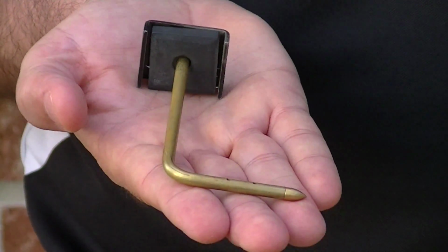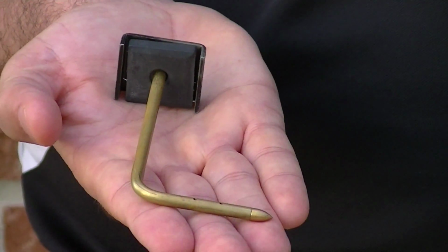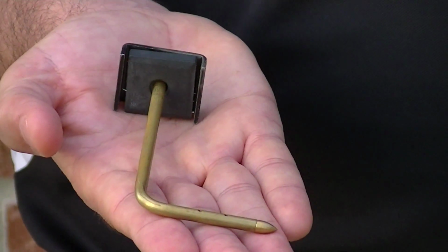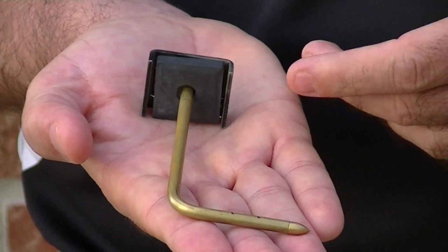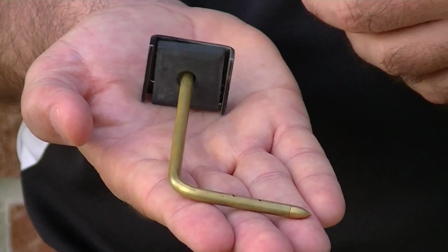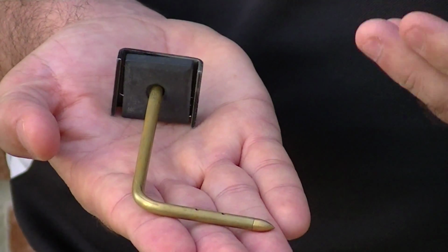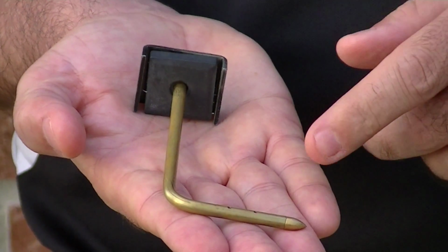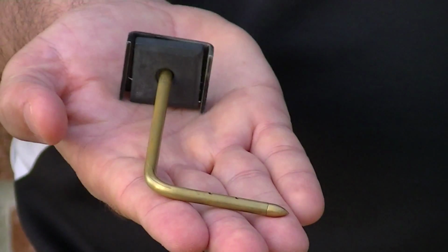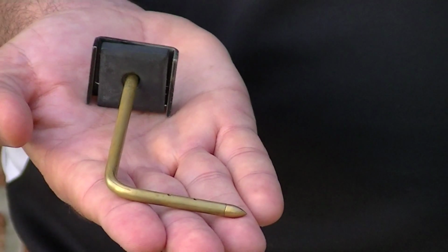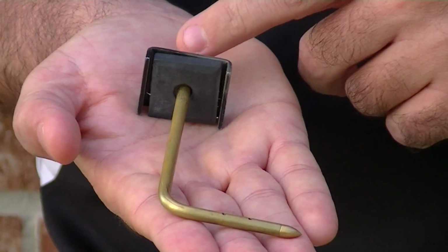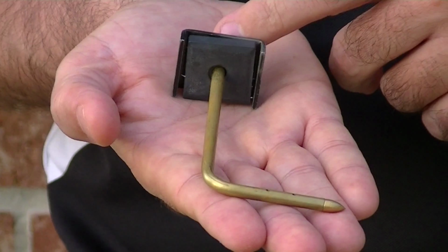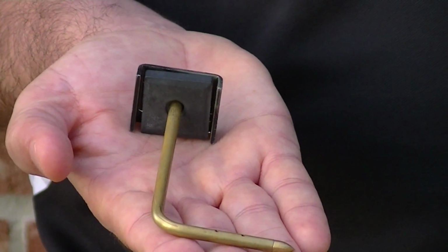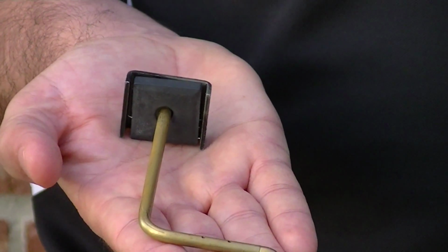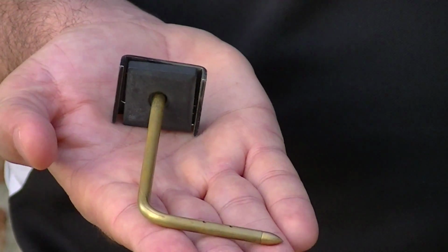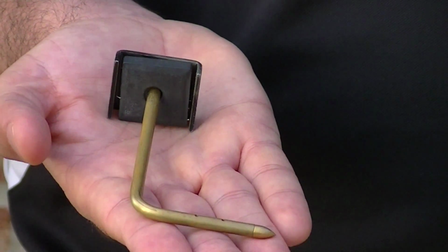The reason why is that most HVAC technicians are trained to insert their pressure probes that way, and you're going to be measuring it in the same orientation. If you change the orientation of that probe, you're going to end up with a different pressure reading than what they got, just because the turbulence is different in the different zones. So this is going to get inserted in the supply plenum, return plenum. I use two probes, one for the supply, one for the return, connect them here with the tube to my DG700 gauge. I've compared the DG700 with a Magnehelic. They're going to be just about dead on if you do the exact same orientation and place them in the same position in the return plenum and the supply plenum.